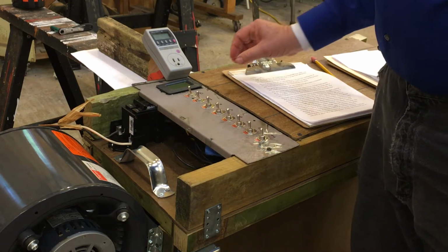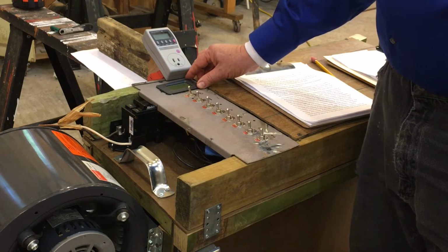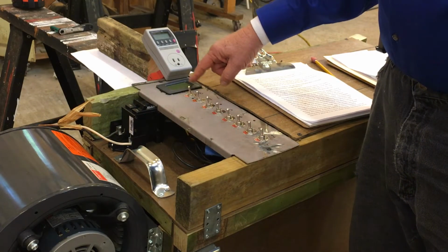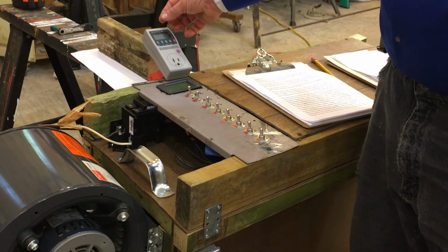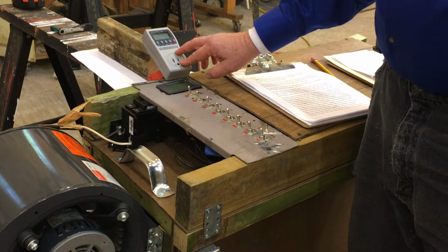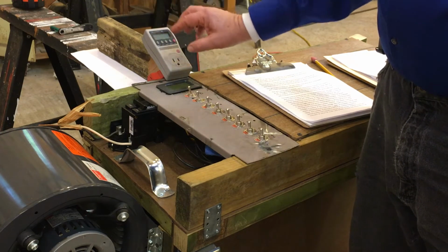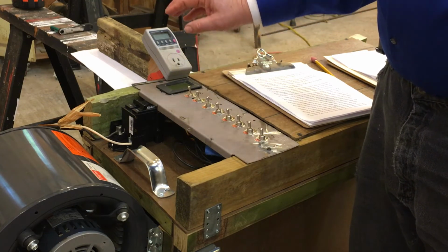The monitoring equipment includes this little electronic load monitor, which gives a readout of voltage. It gives current, kilowatts, kilowatt hours consumed, and also indicates frequency. However, the frequency on this little device seems to be just an indication of whether you're connected to a 50 hertz system or a 60 hertz system, and it doesn't really give you a reading of the frequency. So for that purpose, I brought in this Kill A Watt unit that is commonly available. It's a very nice unit, and by punching the buttons on this, I can see what frequency the generator is producing.